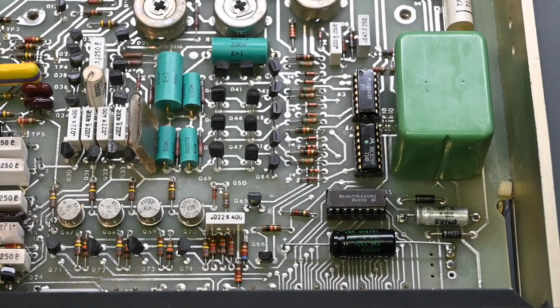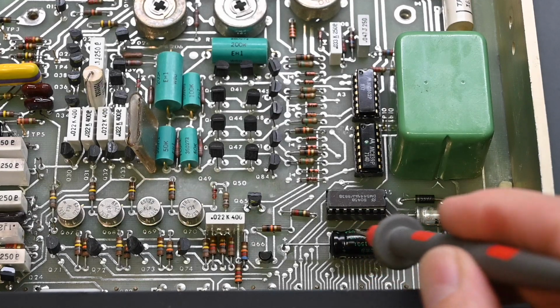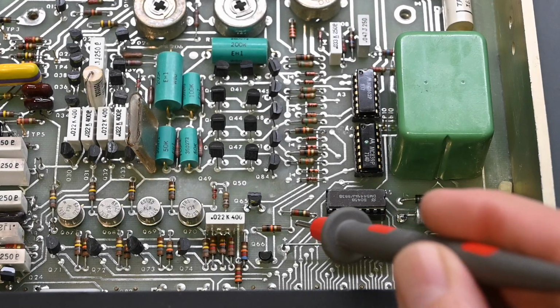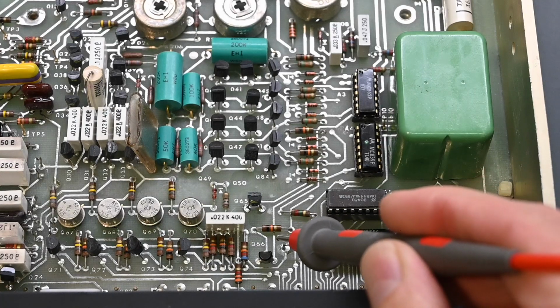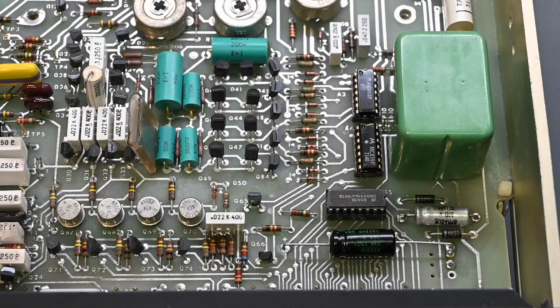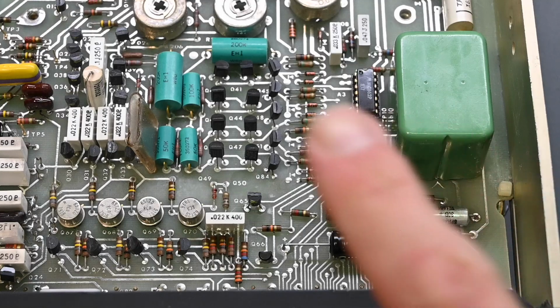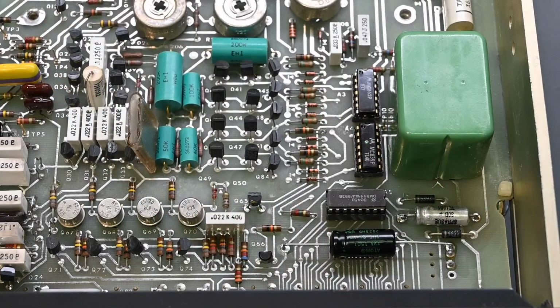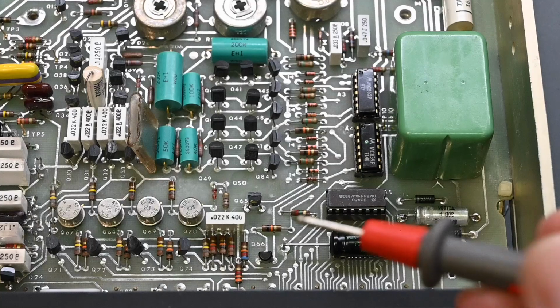But going back to the circuit board right here, when I was taking the measurement, this is the 200 volt capacitor. It's been changed. This is the positive side over here. You can see a little positive mark on the board right there. Now the negative test probe was over in that far corner of the board on test point number 1. That's just a circuit common for all the power supplies. So again, the negative was clipped onto test point number 1, and I came in with this test probe right here.